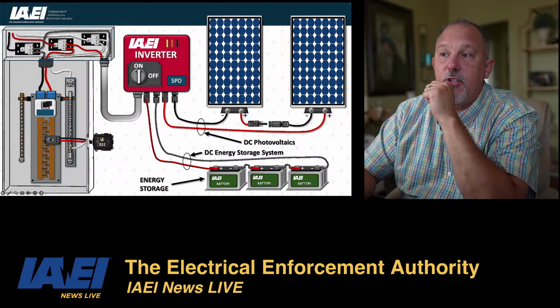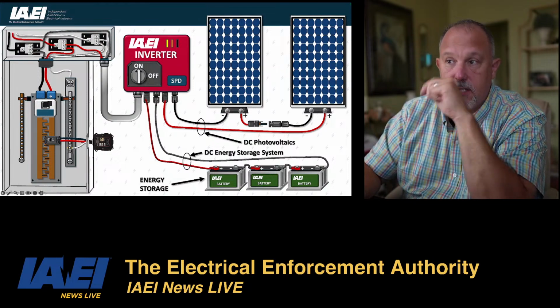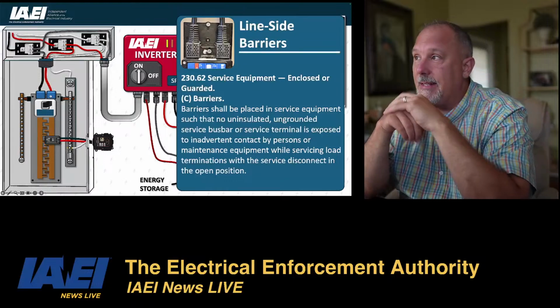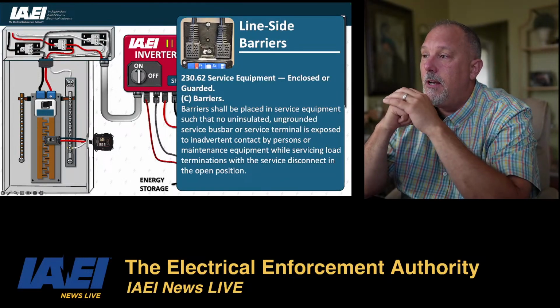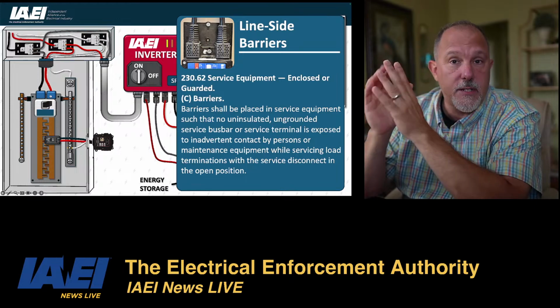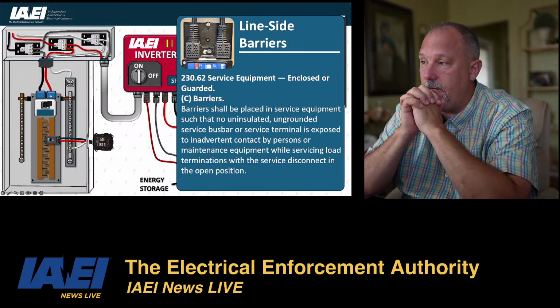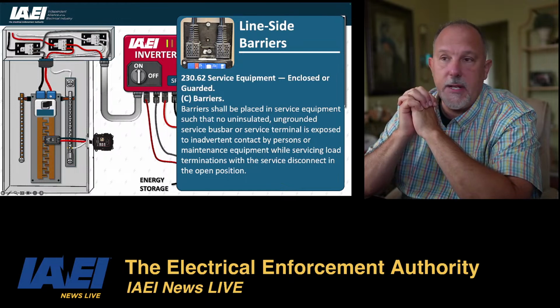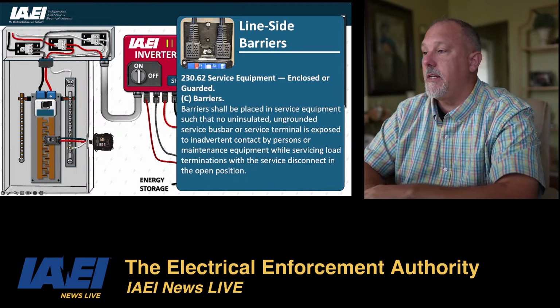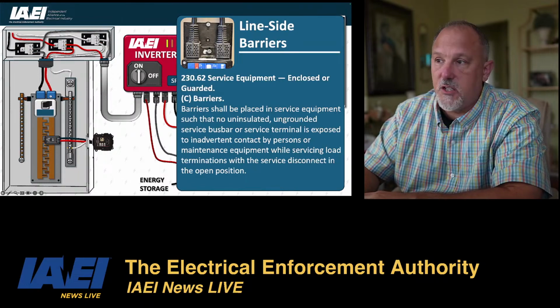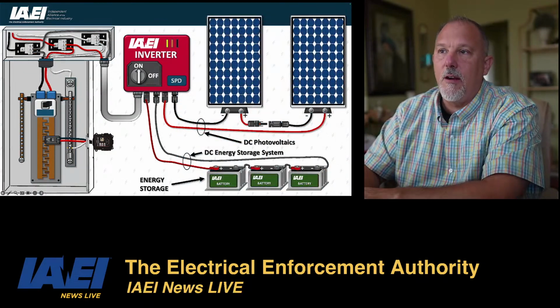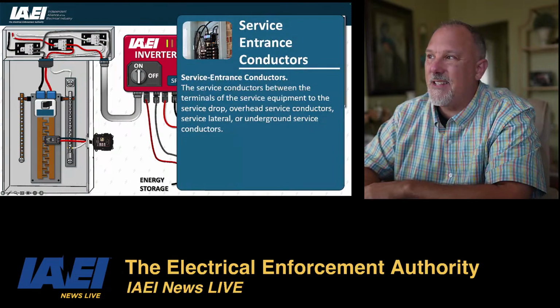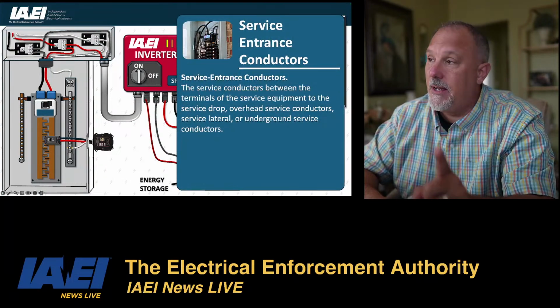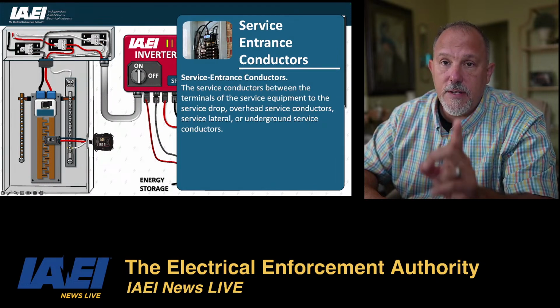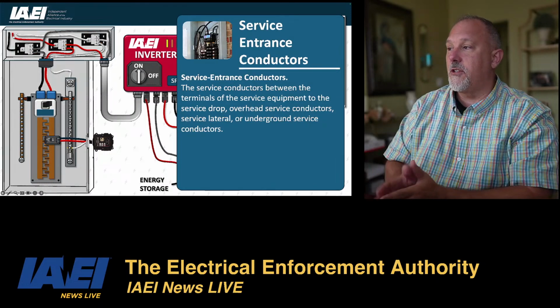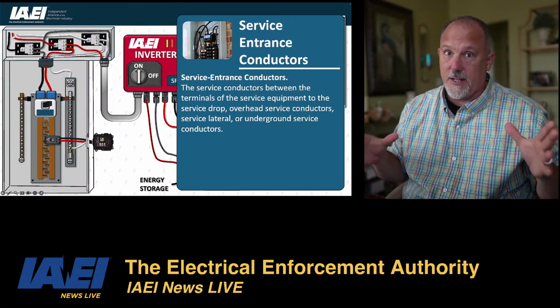Now, what I am showing here, and let's focus on the service equipment. I have the line side barriers. The line side barriers are required by 230.62 because it's service equipment, enclosed or guarded. You have to put barriers in place on service equipment such that no uninsulated, ungrounded service bus bar, etc. is exposed. So that's that requirement. Let's start up here. These are service conductors. Those are service entrance conductors. Service entrance conductors are service conductors. So they're all service conductors.